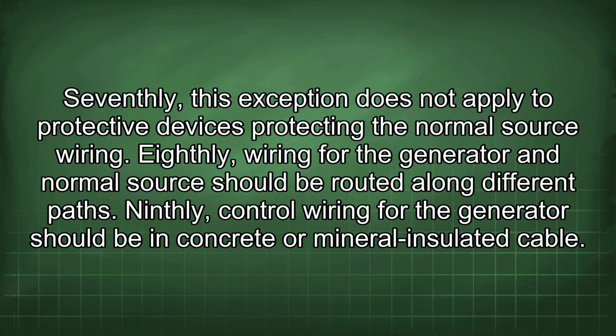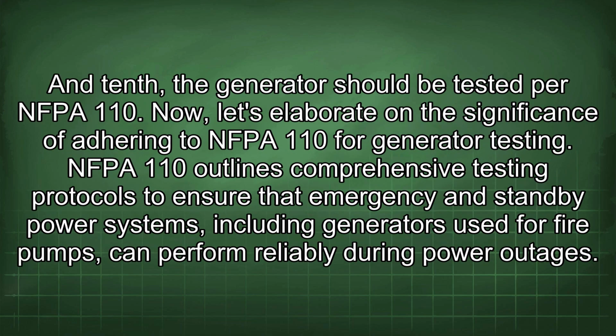Eighthly, wiring for the generator and normal source should be routed along different paths. Ninthly, control wiring for the generator should be in concrete or mineral insulated cable. And 10th, the generator should be tested per NFPA 110.